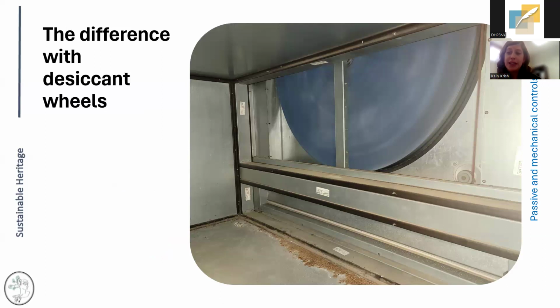Okay, I'm going to make a side note tangent that probably won't apply to most people, but I was worried that if I left it out, there would be somebody this would impact. So desiccant wheels are another option aside from cooling coils. We've run into them a handful of times. They're not super common, but they can be useful. Typically, desiccant wheels are used in places where you either have a really high moisture load, so if you're somewhere where the outside air is just always really humid, or you're trying to achieve a really low relative humidity.